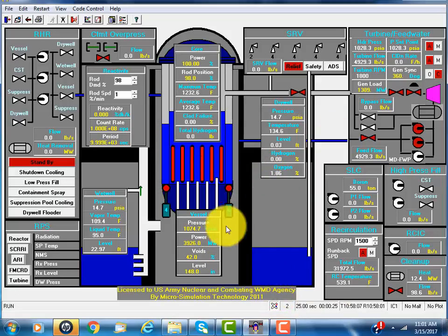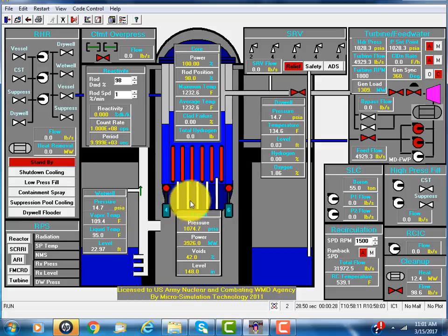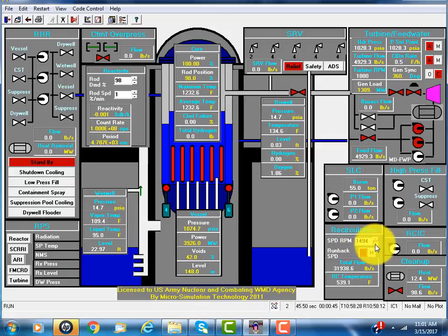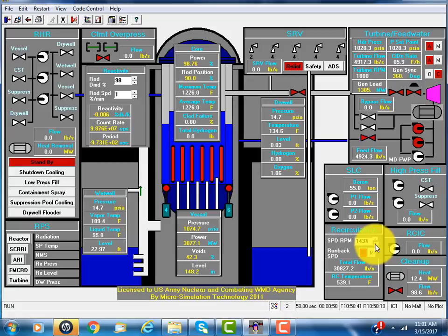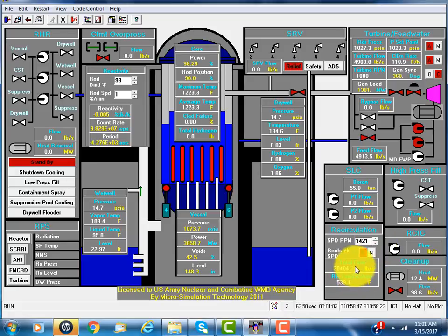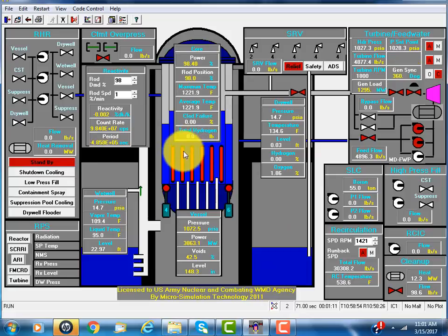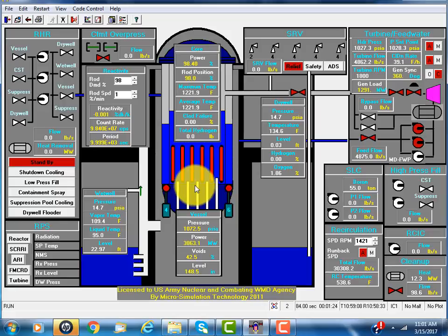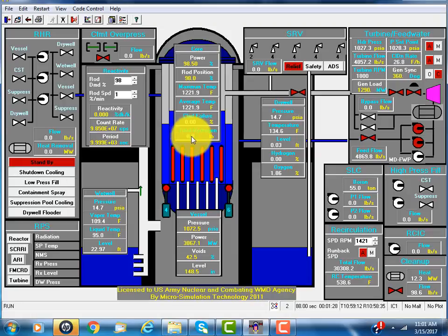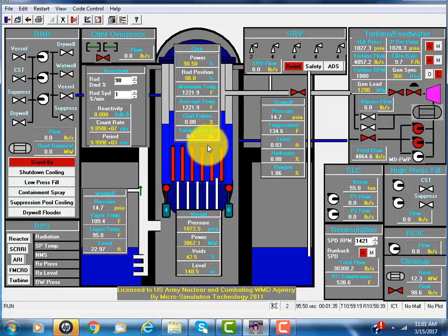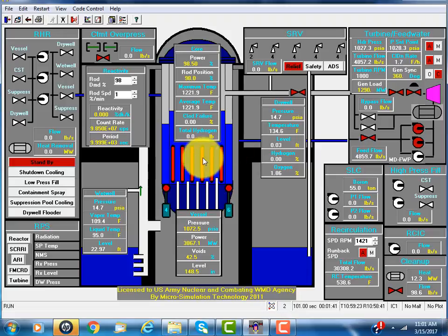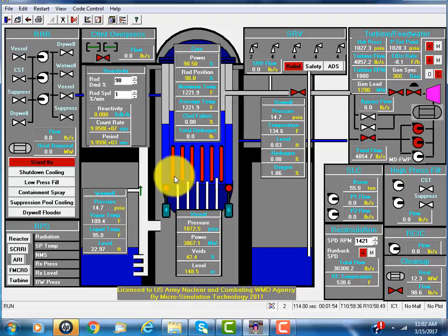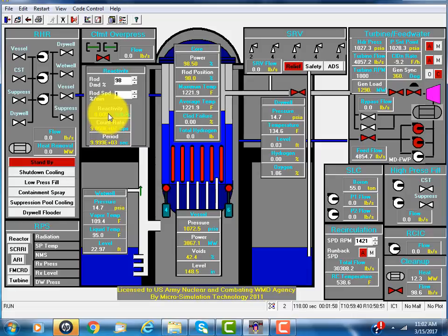For BWR control, we vary the recirculation pump speed. Full speed is 1,500 RPM. Suppose we reduce it to somewhere around 1,400. You see the flow goes down. As a result, there are more voids generated inside the core. The voids have lesser moderator capability than the water, so the reactivity feedback would be negative and the power goes down.